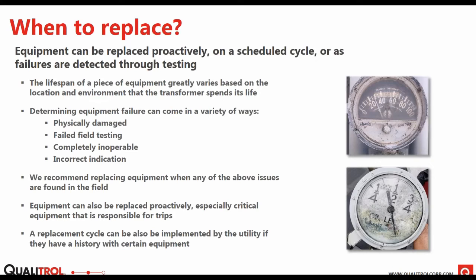Equipment can be replaced on a proactive schedule or a scheduled cycle, or as failures are detected through testing. The lifespan of a piece of equipment varies greatly between environment and location, outside or inside. Some of these can last up to 50 years. Some of them can fail in 20. It all depends on the environment that it's in. If it's in a real dry environment, no ice, no rain, no snow, they could last a very long time.